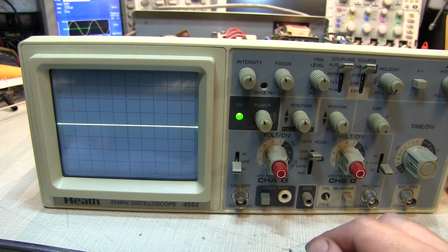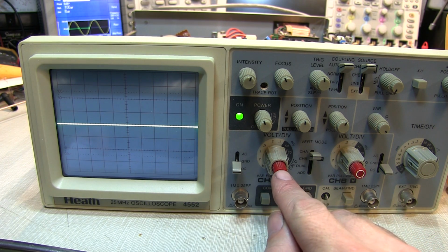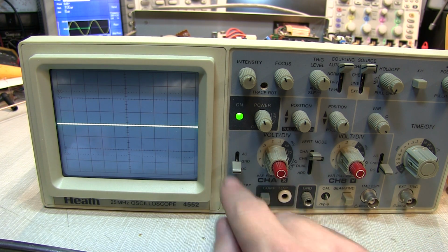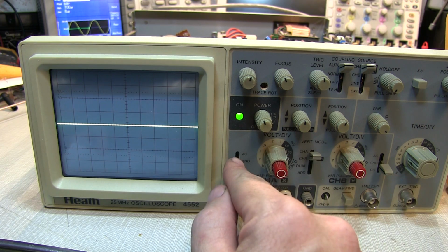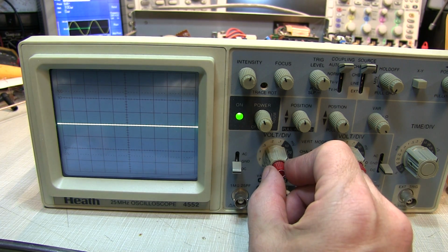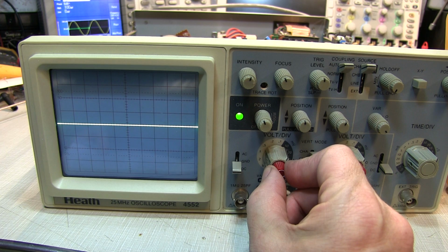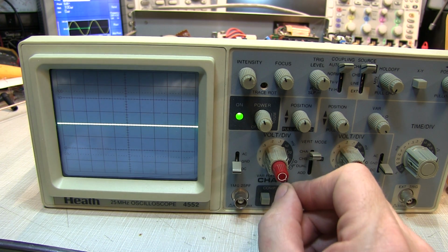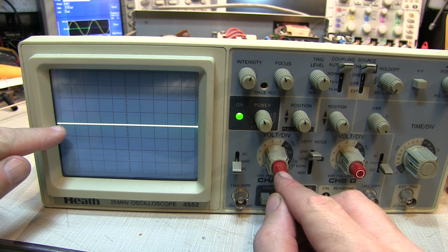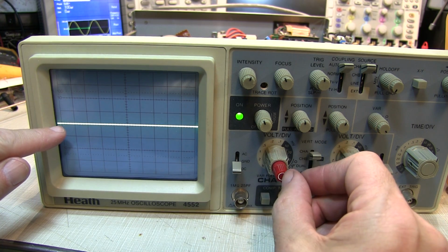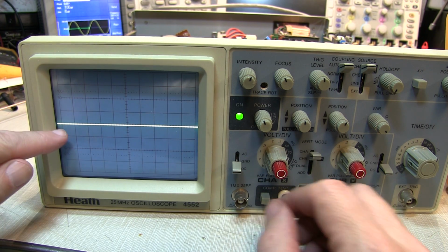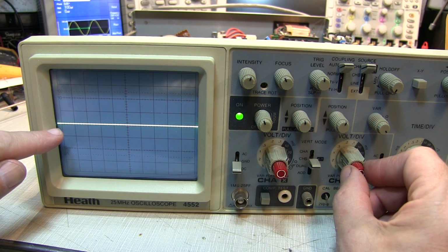So next we'll check the DC balance for the ×5 vertical magnification. So we'll start off on channel A, again with the input grounded, and in this case we pull this knob to go to the 5 times mag, and we noted that we didn't really see a noticeable change in the vertical position. Switch to channel B and do the same thing.